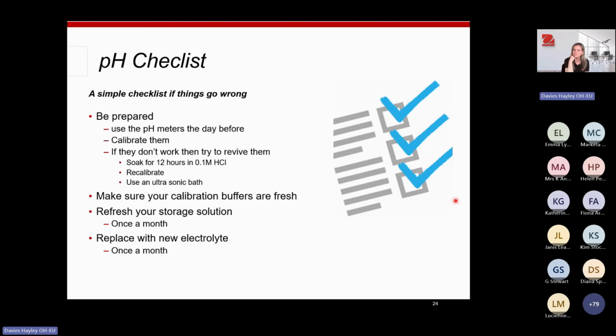Make sure your calibration buffers are fresh. So they can be fresh out of the bottle, or they can be freshly made up using the buffer tablets. And refresh your storage solution once a month. And also, if you have the refillable electrodes, make sure you replace the electrolyte with fresh new electrolyte once a month as well.